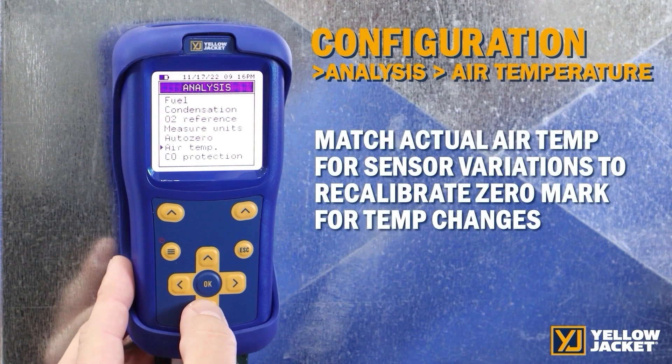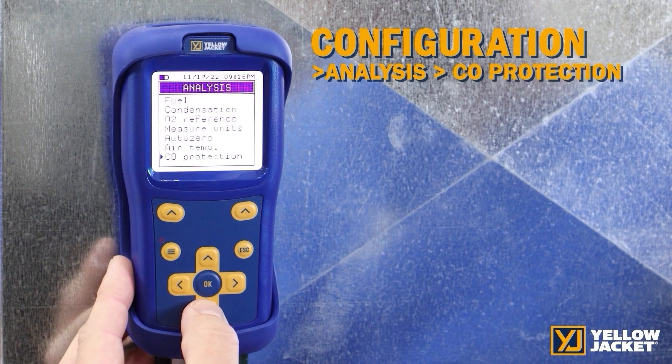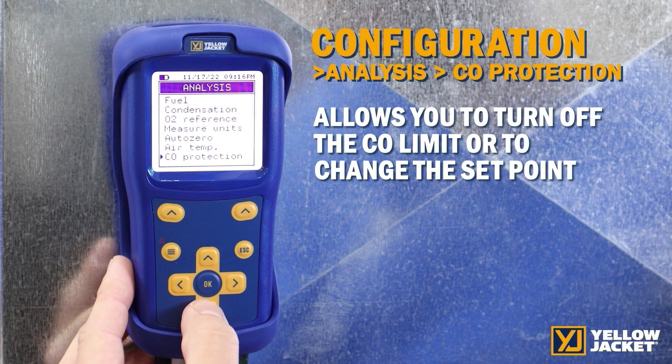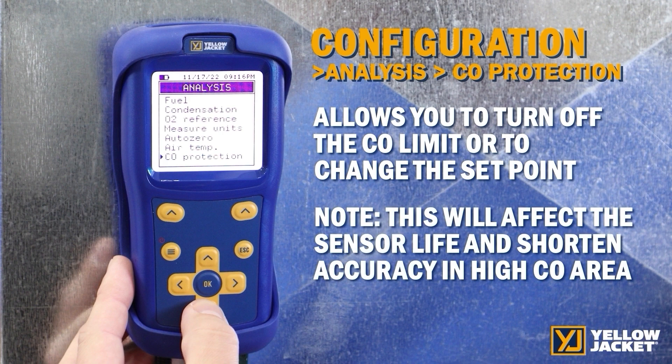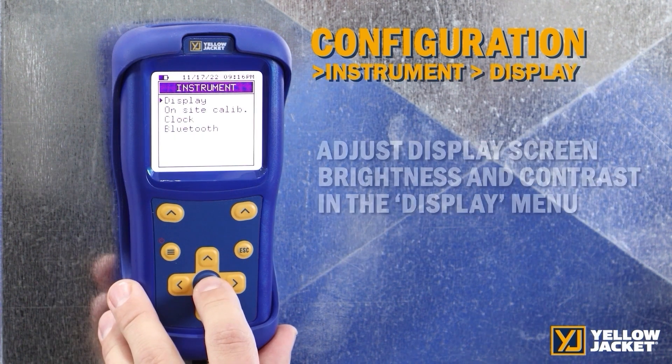Air temp allows you to match the actual air temp sensor variation to recalibrate the zero mark for temperature changes. CO protection allows you to turn off the CO limit or to change the set point. Changing this will affect sensor life and shorten accuracy if used in a higher CO area, as the protection of the device is lowered and more CO is allowed into the sensor.